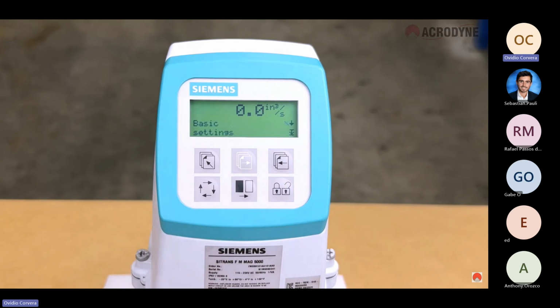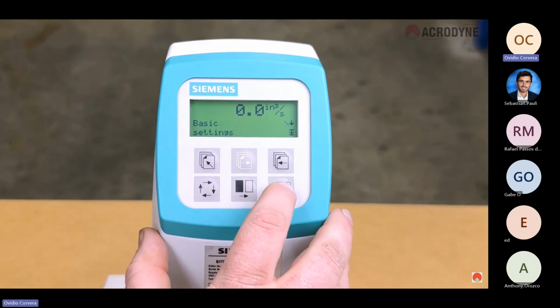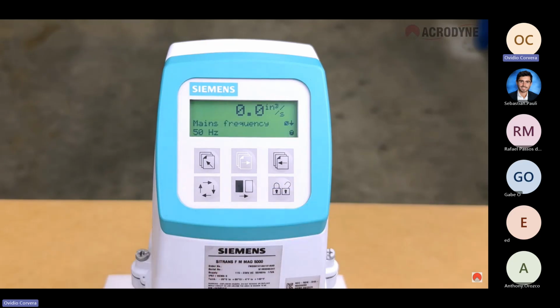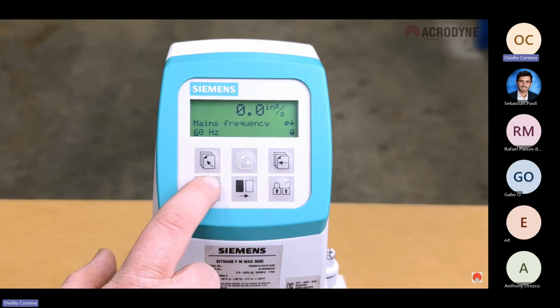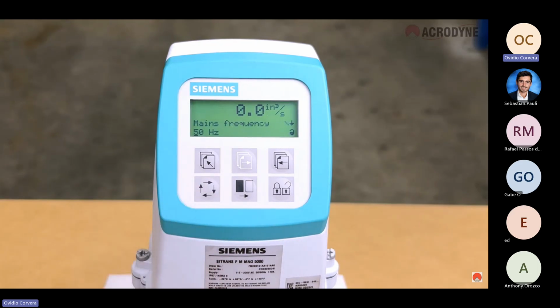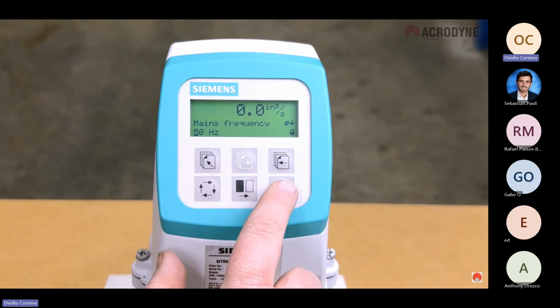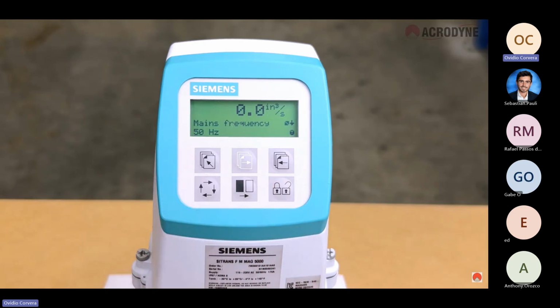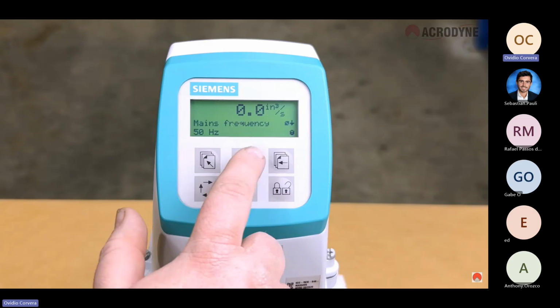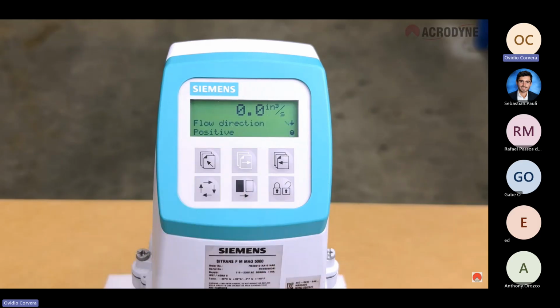The first available option will be the mains frequency. To edit this again, press the lock-unlock button and then press the change key to cycle between 50 and 60 Hz. Please choose the correct mains frequency for your region. In Australia, it is 50 Hz. Press the lock or unlock key again to save the desired setting. Next, press the forward key to edit the next parameter.